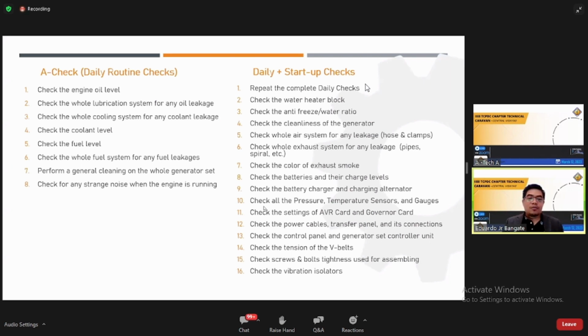So now, what about the daily plus startup checks? So for startup checks, you have to repeat the complete daily checks. Check the water heater block. Check the antifreeze water ratio. Check the cleanliness of the generator. Again, check the whole air system for any leakage, hoses and clamps. Check the color of the exhaust smoke. Later, I will discuss the significance of the color of the exhaust smoke. We have to check the batteries and their charge levels. Again, if this is a backup generator, normally there is an external source for our battery charger. If it is prime power, of course, it will take the charging voltage from an alternator. So you have to check that one.